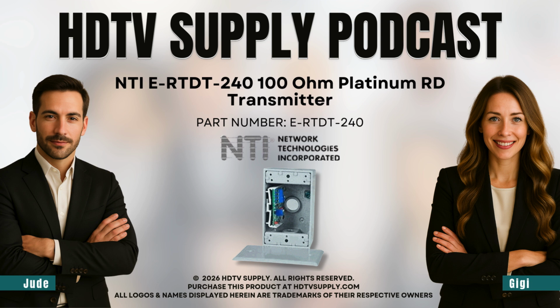Perfect. Okay, let's talk about the signal itself, the 4-20 milliamp standard. Why use that instead of, say, a simple voltage signal? That's the key for long cable runs. A voltage signal degrades pretty badly over distance. Imagine running cables hundreds of feet through a factory floor with tons of electrical noise. It's like a weak AM radio signal fading in and out. Right, you lose the information. You lose it. But the 4-20 mA standard is a current signal. Current is way more robust against resistance and noise. It basically guarantees the signal that arrives at the monitoring station is identical to the one that left the sensor. It's all about data integrity.